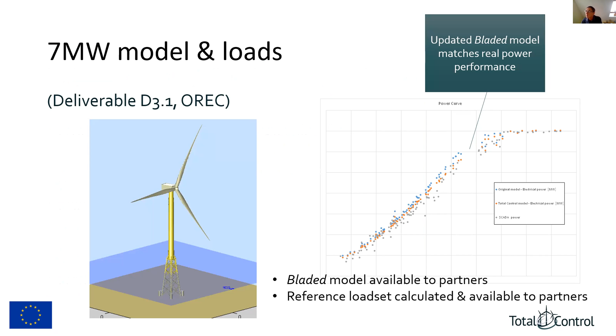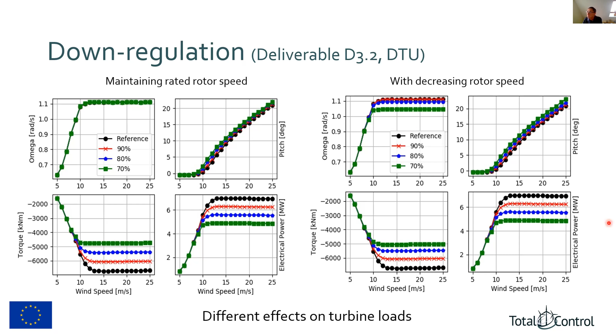This is the down regulation, the reduction of rated power, and DTU did a study looking at 2 different algorithms for this. On the left is maintaining — let's get the pointer — this is keeping the rotor speed constant, changing the torque and hence the power, and this is the change in pitch angle that you get. On the right is allowing the rotor speed to decrease, shown in this graph. So as you decrease power, you also decrease rotor speed, and that can be beneficial for loads. The point of this is to look at different load effects.